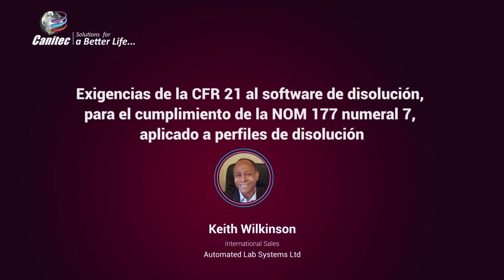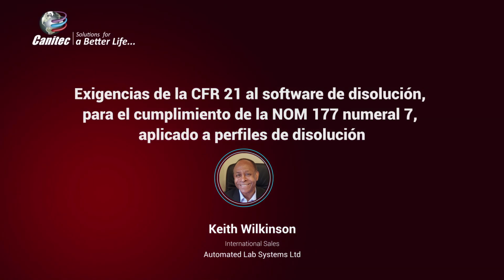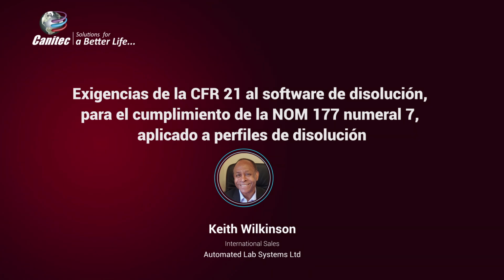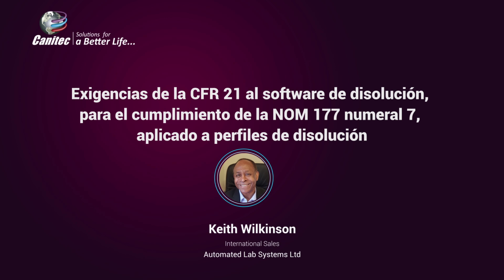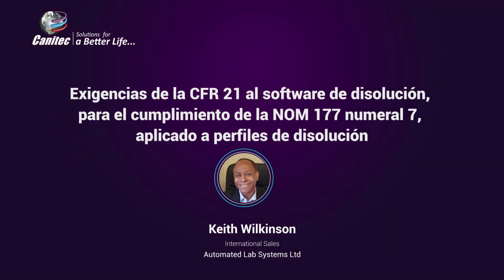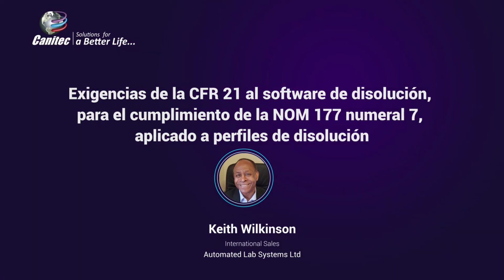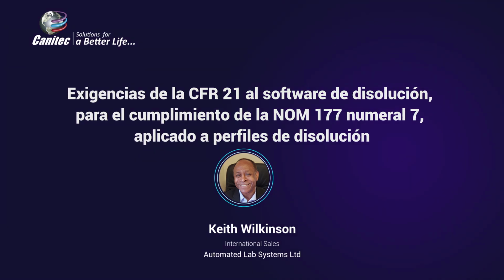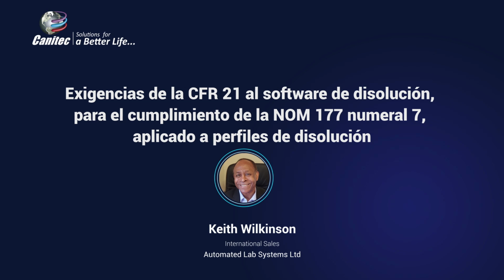We have, I didn't show you, but in the software, you can configure the specification for the testing. And you can see at the end whether or not the sample complied with that specification. There's another big part of the software which I did not show you. The USP compliance tests can also be verified in the other software. For example, let me just show you this.